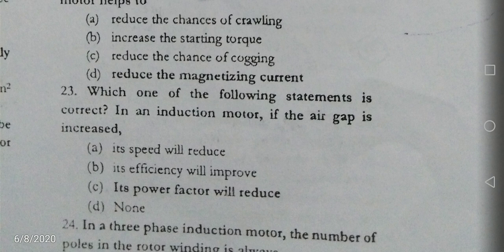No. Its efficiency will improve? No. Its power factor will reduce. So if the air gap is less, then the magnetizing current will be reduced and power factor will be improved. If the air gap is more, magnetizing current is more and power factor is less.